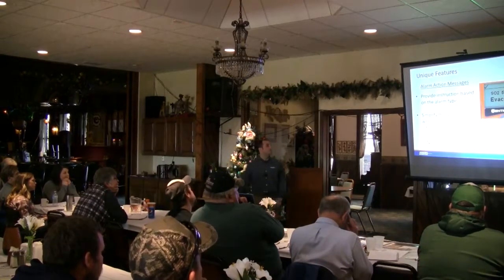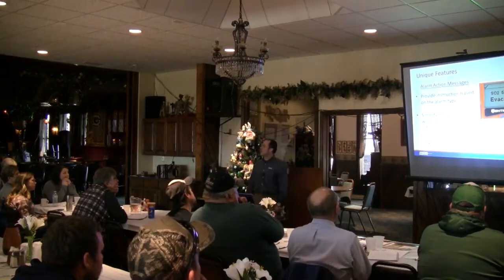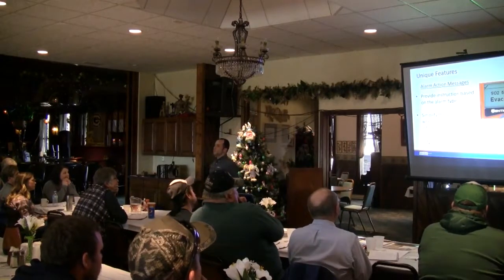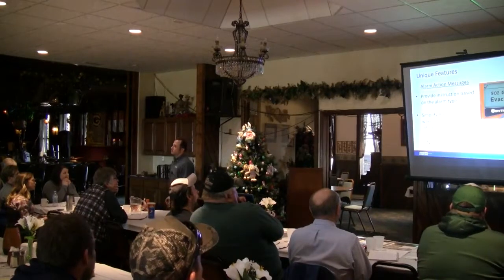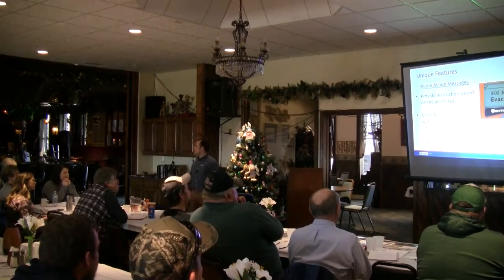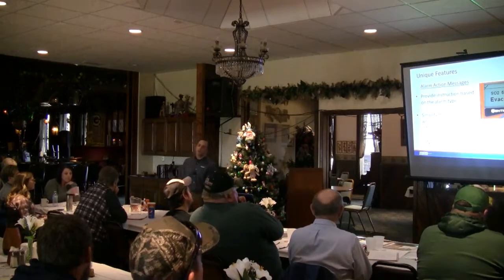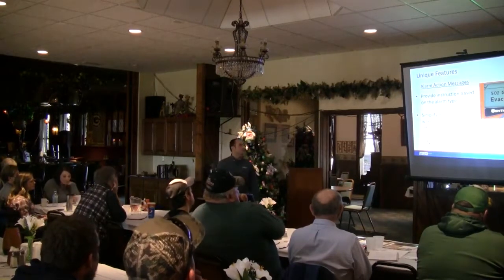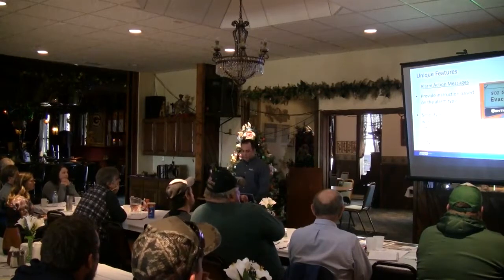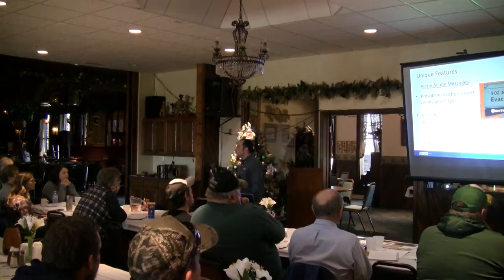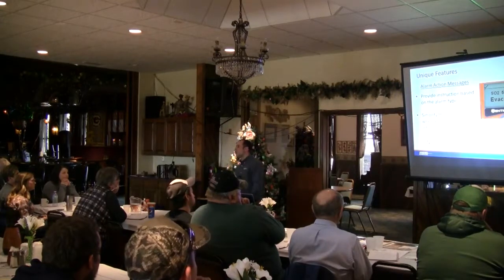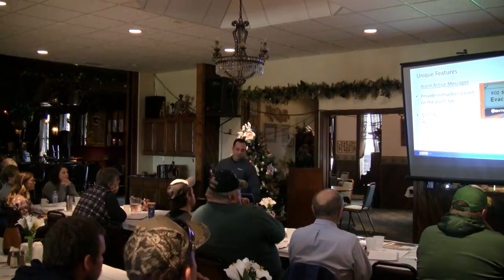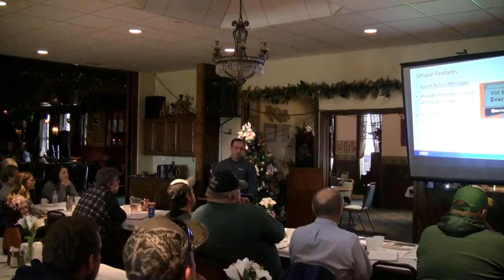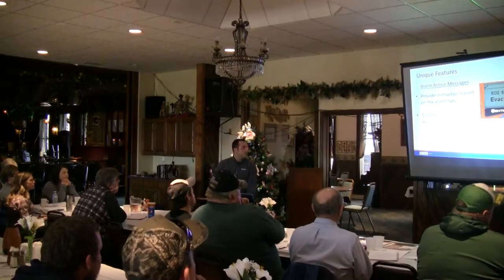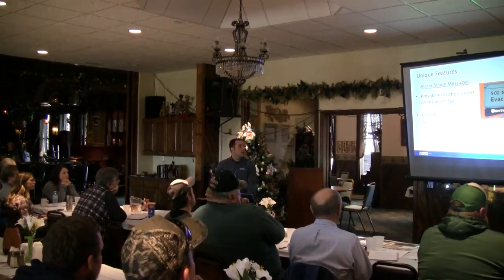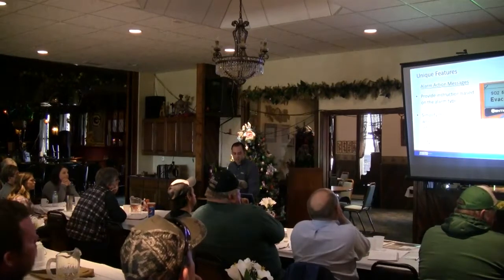Here's that alarm action message, telling you how to respond to that level of gas: turn on the fans, evacuate. If you're using time-weighted average or STEL alarms, which weren't heavily discussed today, it might say stop work for 8 hours, stop work for a day, or stop work and go to the hospital. You can program all that into the device so it tells you exactly how to respond to that level of gas, so you're not guessing or looking at the device wondering what to do.